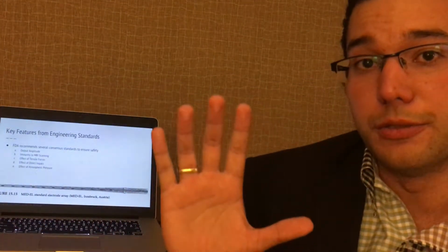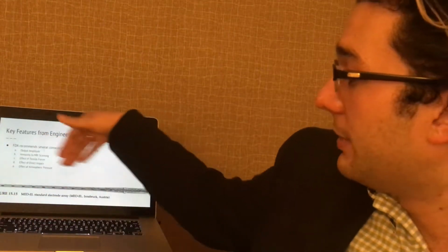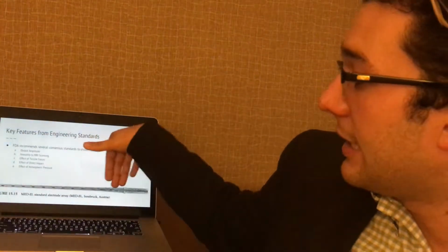For any medical device, the FDA establishes standards and regulations to assure safety for the population and consistency throughout manufacturers. Cochlear implants are no different. For cochlear implants, the FDA recommends 5 different fields that must be tested: output amplitude, immunity to MRI testing, effect of tensile forces, effect of direct impact, and effect of atmospheric pressure. A lot of these tests are actually involved on the probe itself and on the array. Here you can see a sample array where one channel is led to only one electrode, as we've talked before.